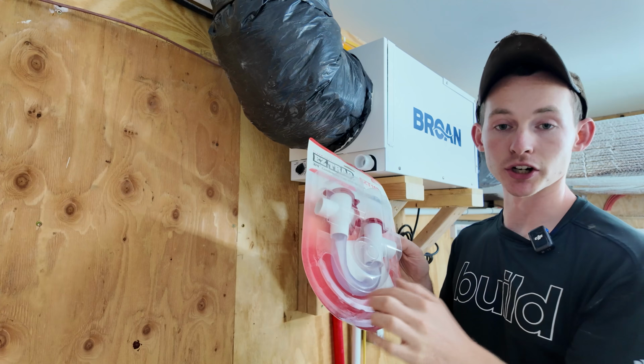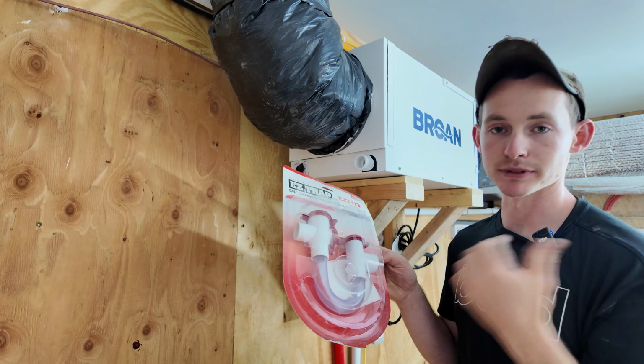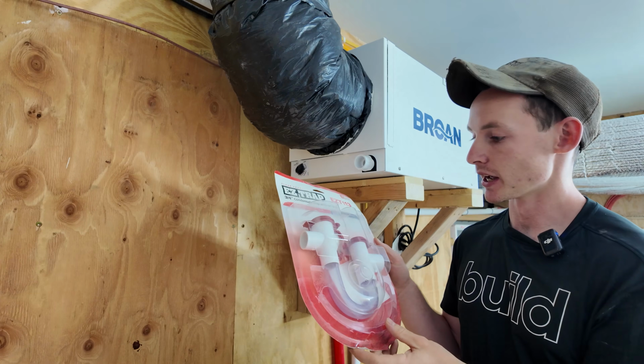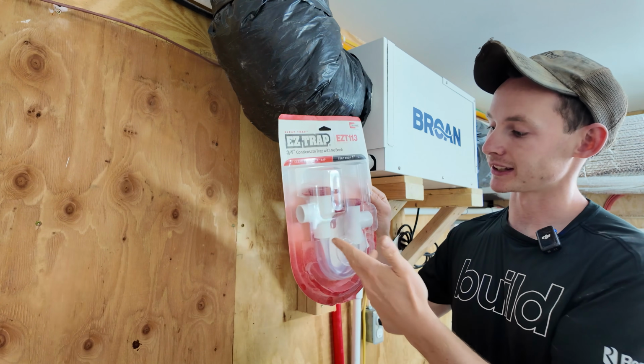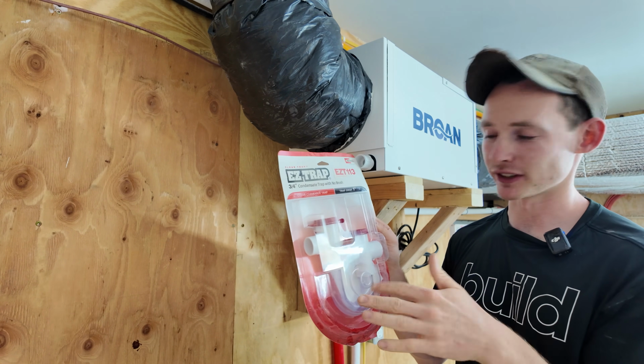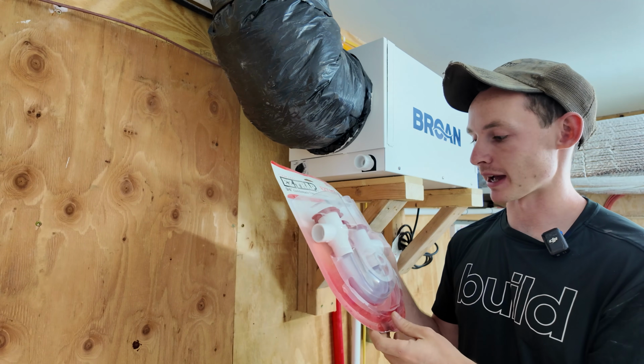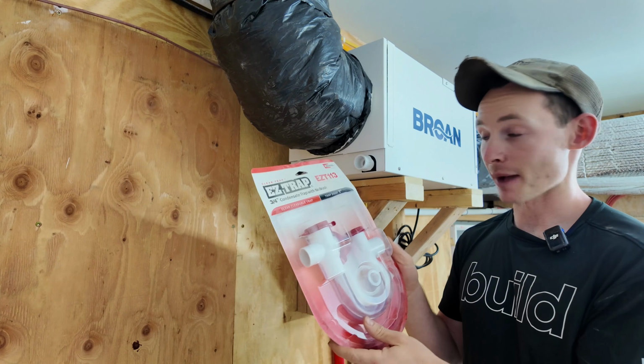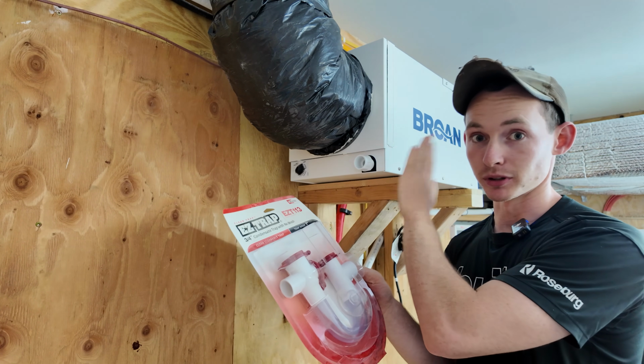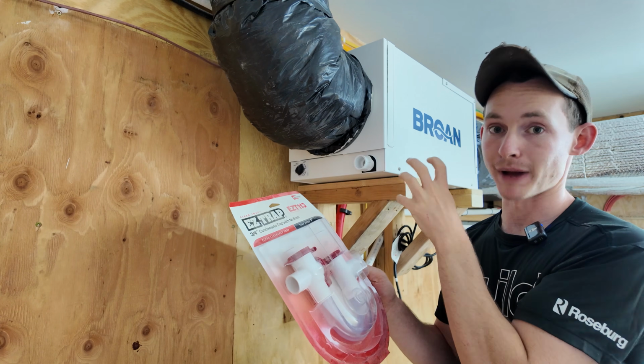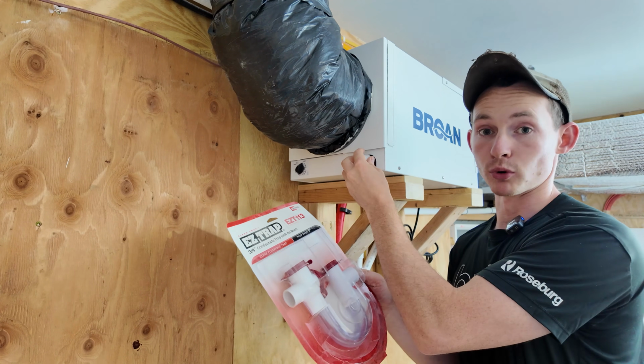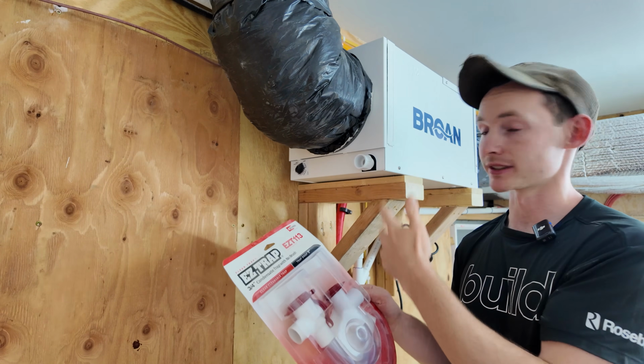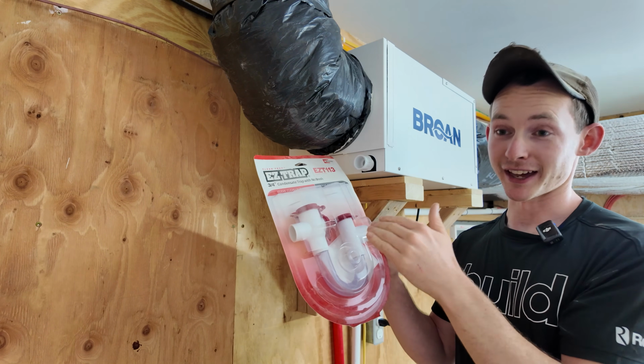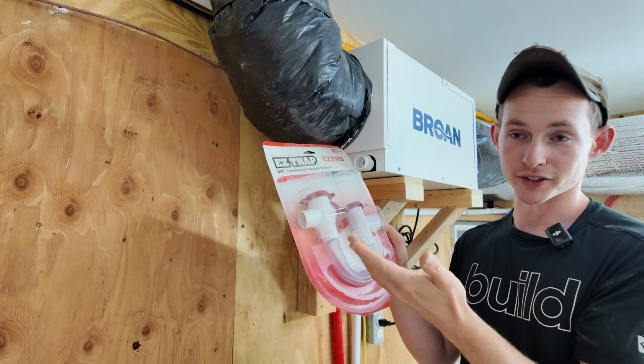It's a clear trap. I got this off supplyhouse.com, same exact one I used for the main air handler. But you're able to pop the tops open if you want to clean this out. They get kind of algae filled after a while, so you do need to clean them out or else they will clog up. But having the trap is necessary for this thing to actually blow properly and develop proper back pressure. Otherwise, this drain would more or less be an open hole into the system it's pulling return air from. So to plug that hole and still allow water to drain, you put a trap in.